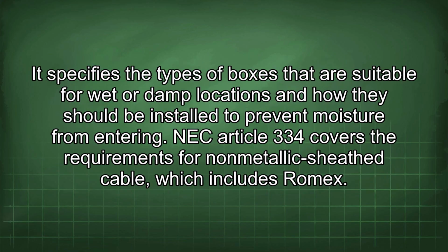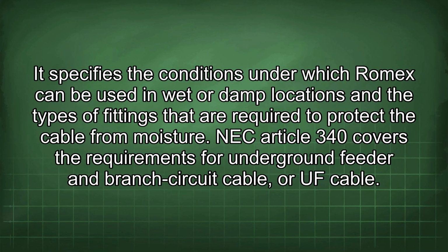It specifies the types of boxes that are suitable for wet or damp locations and how they should be installed to prevent moisture from entering. NEC Article 334 covers the requirements for non-metallic sheathed cable, which includes Romex. It specifies the conditions under which Romex can be used in wet or damp locations and the types of fittings that are required to protect the cable from moisture.